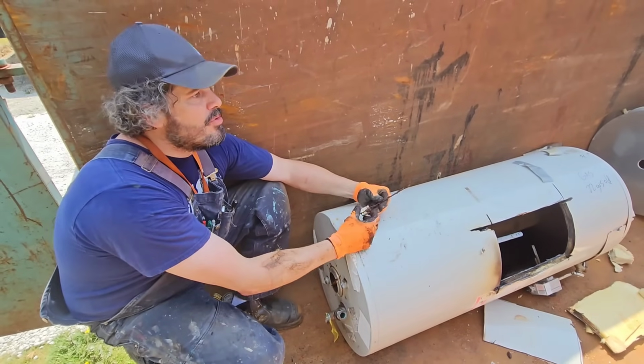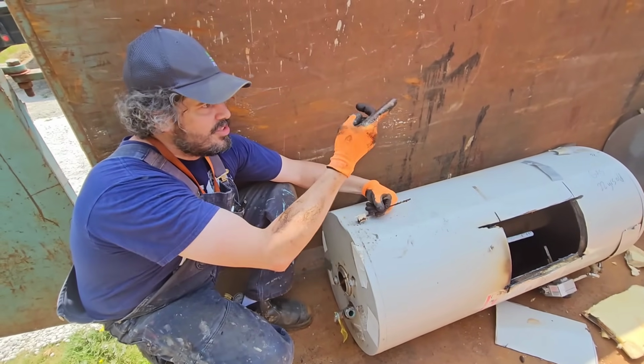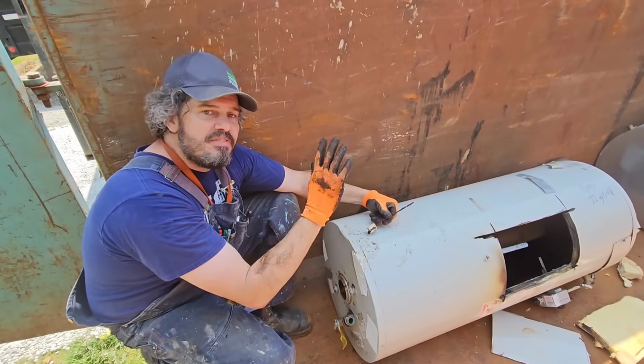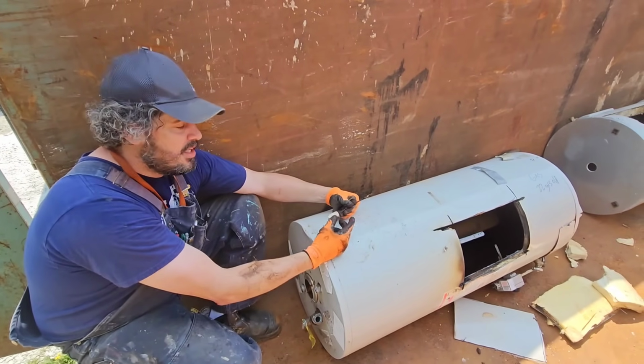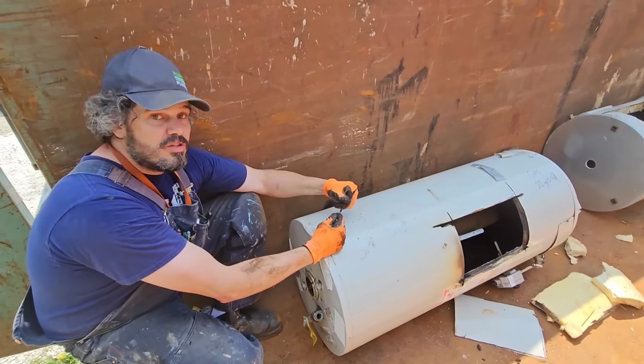Here in the Pacific Northwest, they last for about 15 years. You saw a 12-year-old one, and this is a 22-year-old one. But on average, most of our tanks go around the 15, 16, 17-year mark, that's almost 3 times the warranty period. But there are some well systems out here that would deteriorate this within 3 years.